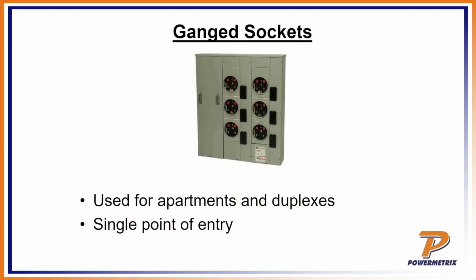SUSE: suitable for use as service entrance, excuse me. So what it tells you is I've got 6 throws of the hand, right? And this goes all the way back to the days of fires. If you think about it, what we see today is developed because back in the day they just had bare wires running everywhere, and the fires were the main problem with trying to first run and use electricity in our country. So the main thing was how many throws of the hand so I can shut everything down if a fire had started. If you go way back, that's where they came up with 6 throws of the hand. So here's a case where, if I've got 6 throws of the hand or less, I don't have to have a main on that far left side, according to the code and SUSE. But if I had more than that, I would need to have some sort of main breaker or main disconnect on that far left.